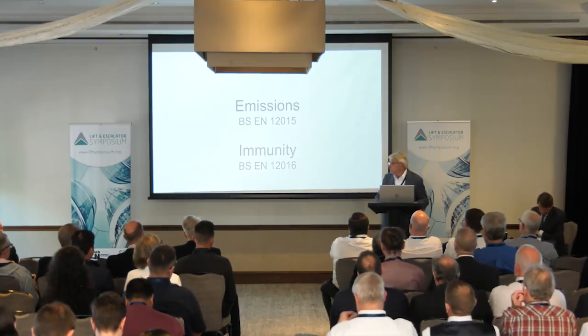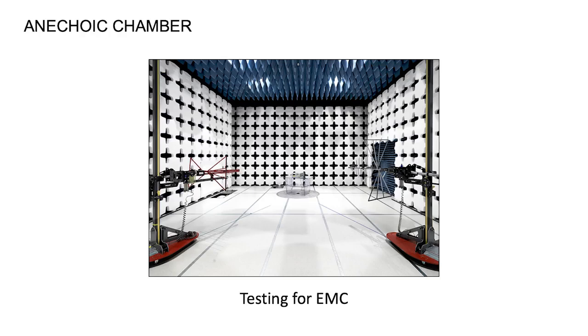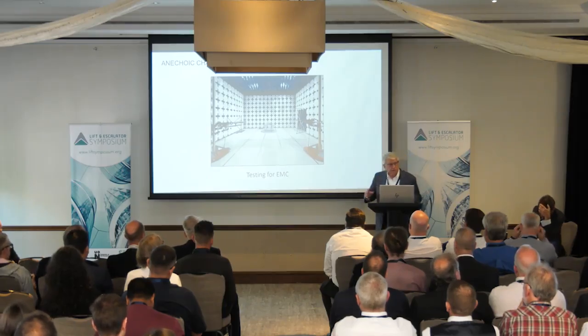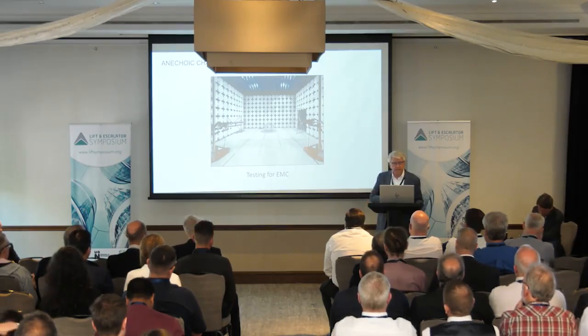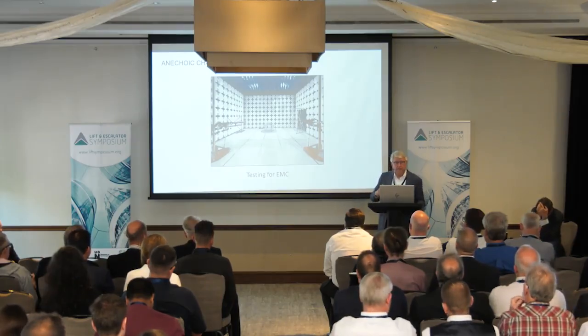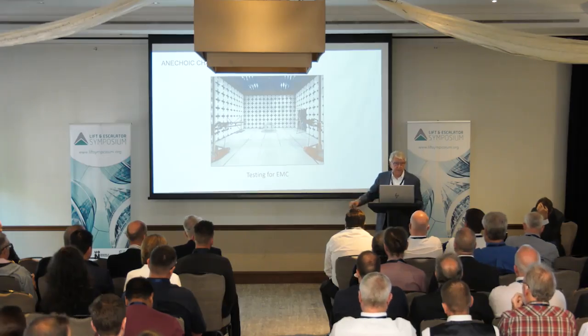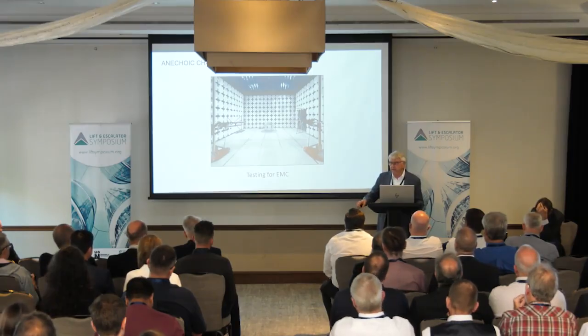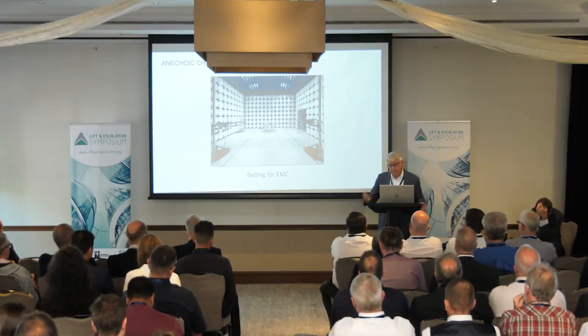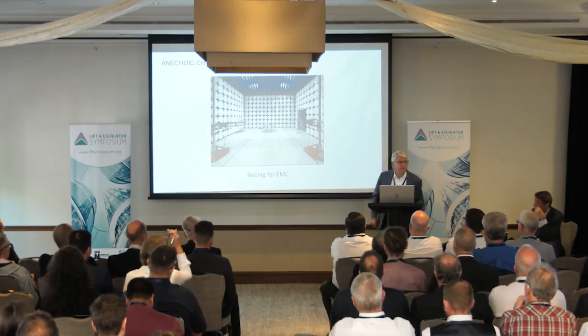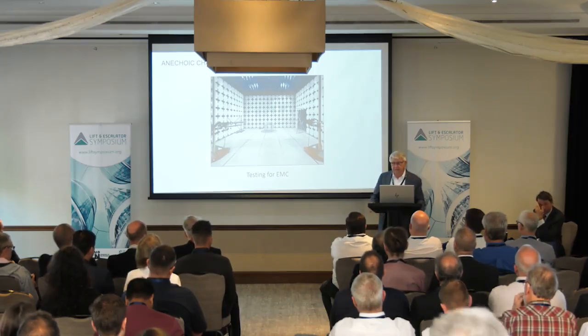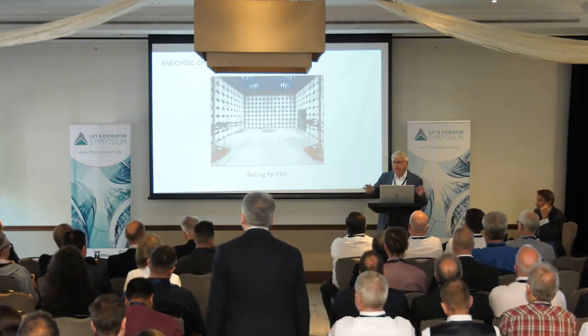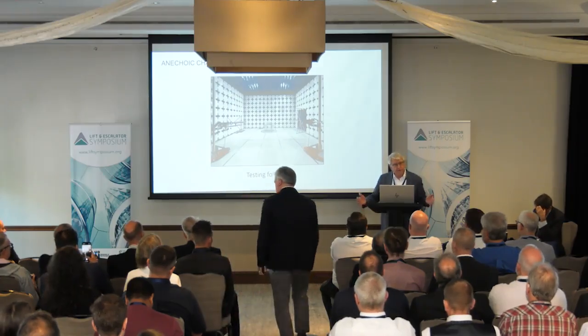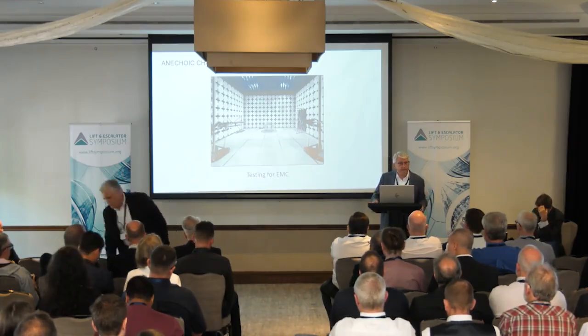They use anechoic chambers for testing EMC. You put your part on the table, and they have various antennas to listen to the noise coming from the controller, over a very wide frequency range, and it has to be below a certain intensity level. They also connect transformers to the three-phase power line and look for noise conducted across the line. Then they turn on a transmitter and try to hit the controller with high-powered radio frequency. It's done inside these chambers so it doesn't radiate and interfere with equipment outside, and so you don't receive any interference from outside.